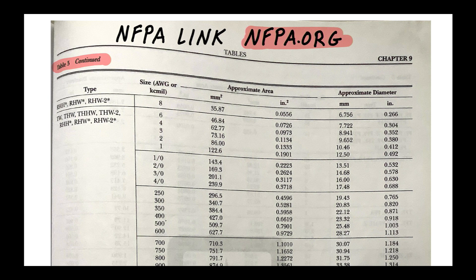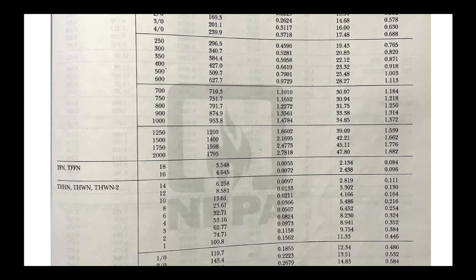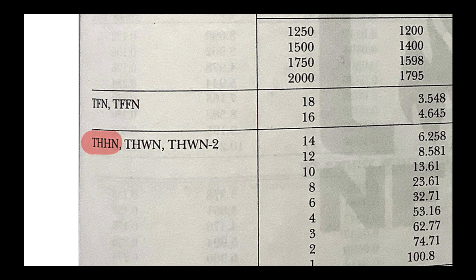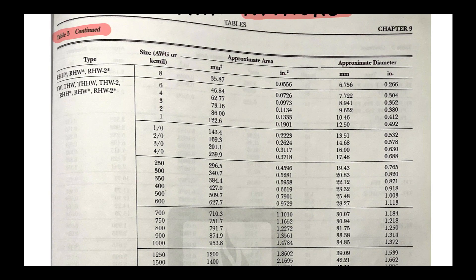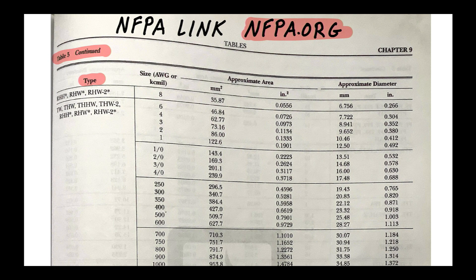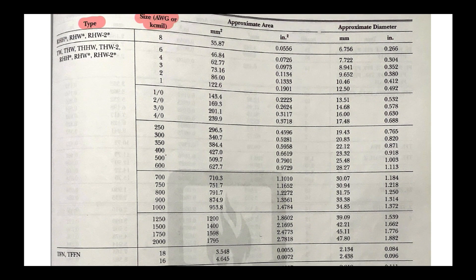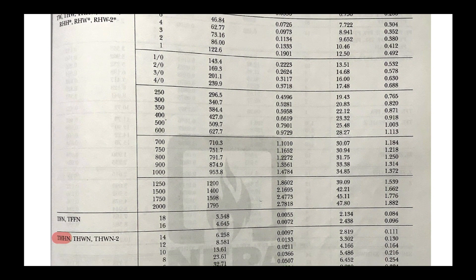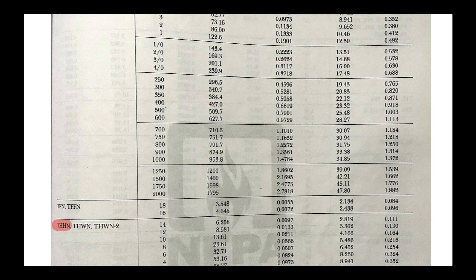Table 5 in Chapter 9 is called 'Dimensions of Insulated Conductors and Fixture Wires.' We were told the conductor we're looking for is THHN, so we find that in the first column under 'Type.' The next thing we look for is the size — we find THHN and then 10 AWG.